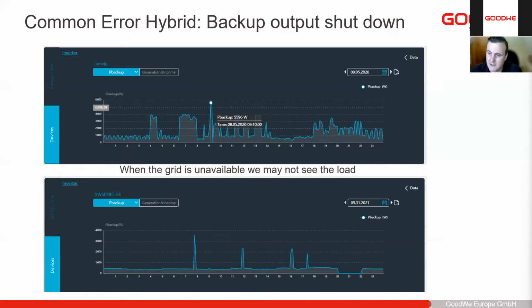Please note with a shutdown like this, if you are experiencing it, please don't manually restart the inverter and switch it back on. That is very often the customer's natural reaction: switch everything completely off and switch it back on again. If you do that, then you clear the recovery error, so you can't see the reason why it shut down.